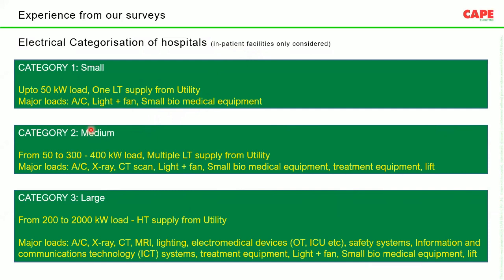equipment. And the next level is the medium-sized hospitals, where the connected load is 50 to about 300, 400 kilowatts. Here the problem is, instead of going for a high voltage supply, most often each building, or each part of the building, has multiple LT supplies from the utility; multiple low voltage, low tension supplies are taken. Once multiple supplies are taken, sometimes the wiring practices are not followed properly. In these hospitals, the majority of the load is air conditioners, then X-ray machines, CT scan, light fittings and fans, small biomedical equipment, and so on.